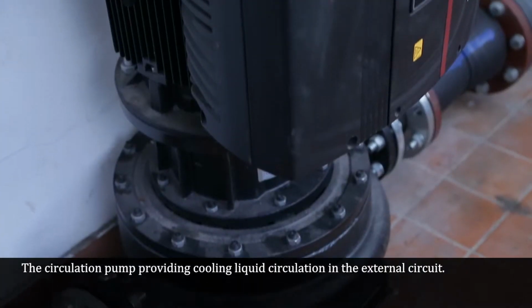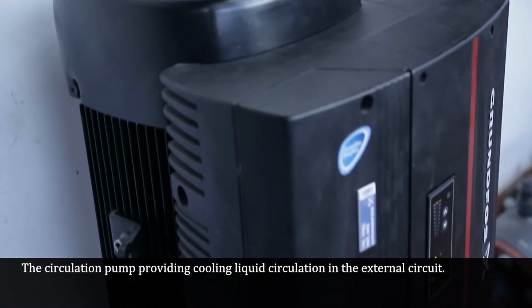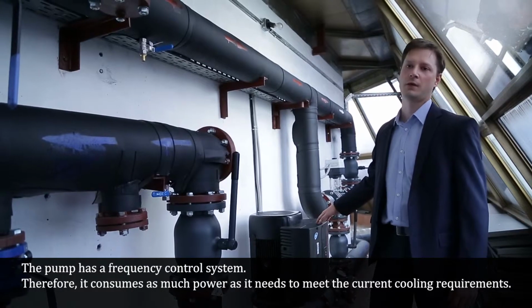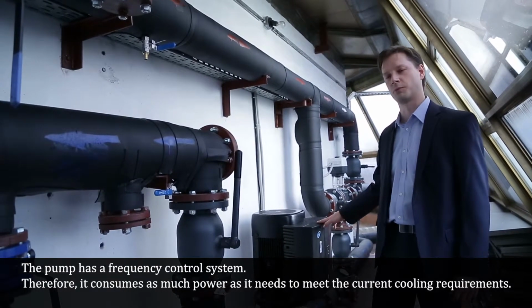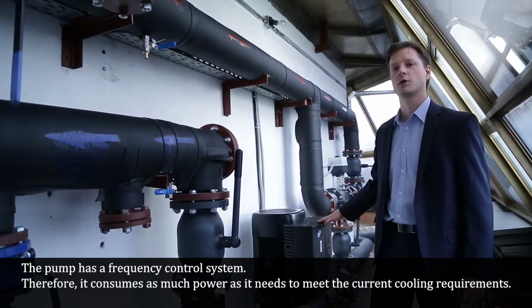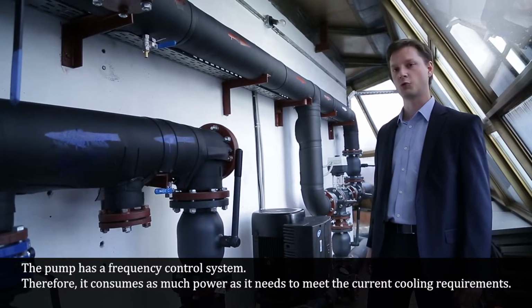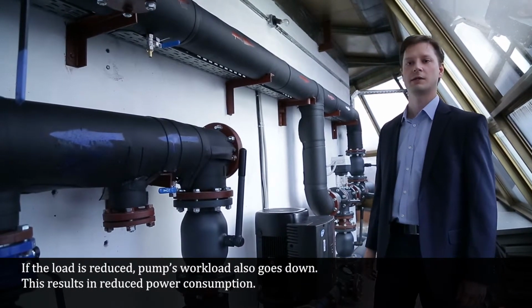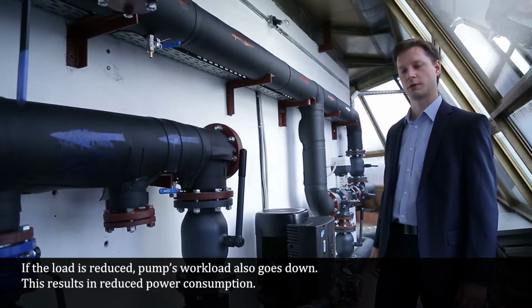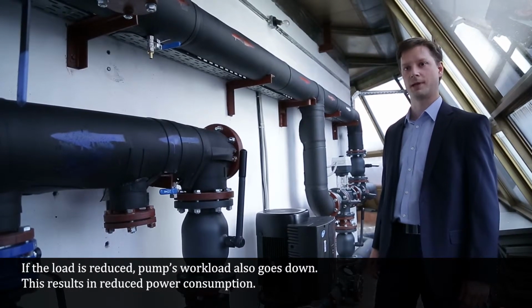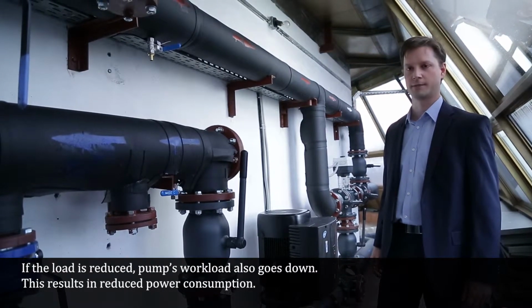The circulation pump provides cooling liquid circulation in the external circuit. The pump has a frequency control system. Therefore, it consumes as much power as it needs to meet the current cooling requirements. If the load is reduced, the pump's workload also goes down. This results in reduced power consumption.